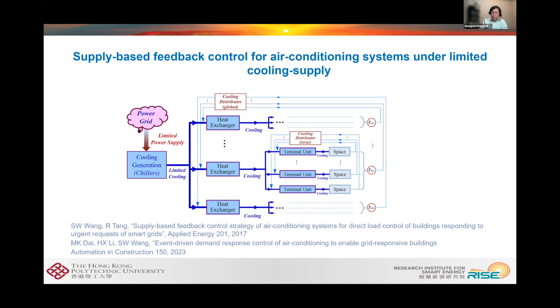To solve this problem, we developed two generations of control strategies. The first generation is the supply-based control, which I show here in the PowerPoint. But the problem with the first generation is that it cannot be directly implemented on DDC controllers, because it needs a little higher computing power. So it's not so practical to implement in buildings with DDC controllers. Therefore, we developed the second generation, a control logic called reconfigurable feedback control strategy, which can be deployed on conventional DDC controllers.